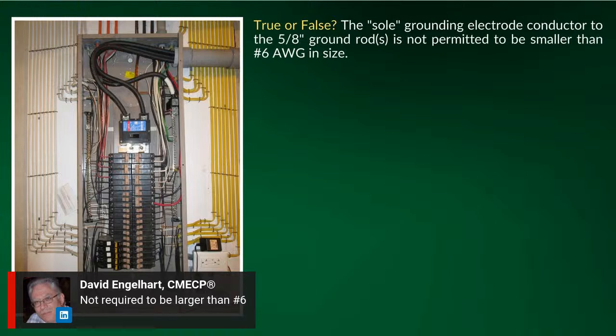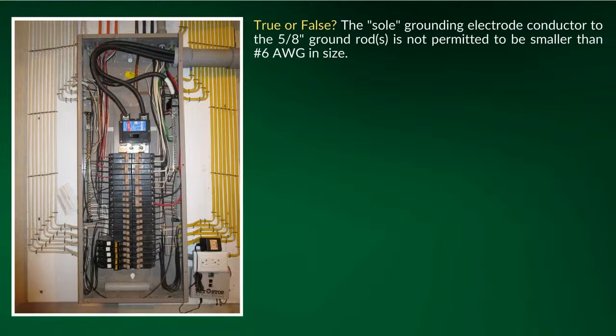All right, David Englehart. Awesome. Yeah, and that's true. It's not required to be larger than number 6. So where this comes in, where we learned from Senior in the podcast that he did, basically the reason why they made electrodes out of the table was because people were running too large a conductor to them, and they weren't making good connections. So I can just imagine, if people could picture running like a 3/0 to a ground rod, that wouldn't make good sense.